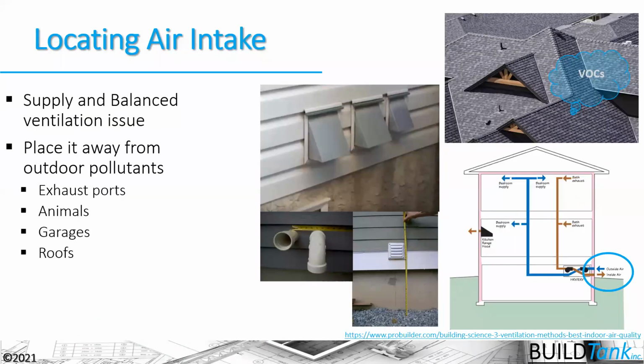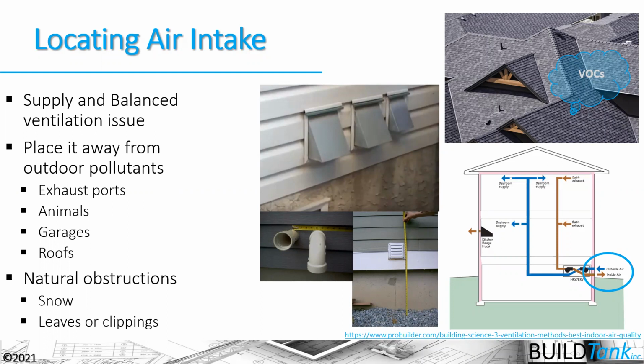We also need to think about where that air intake is coming from. The code gives us an idea of how to stretch it from the exhaust duct: it has to be at least 10 feet horizontally and 3 feet vertically away. But we also don't want to take it from roofs that might be off-gassing oils and other things. Those asphalt composite shingles are not a great place to pull your air from. Pet runs, garages, other places we don't want to run that. And then we need to think about obstructions that might happen at those fresh air ports with snow and leaves and other things.